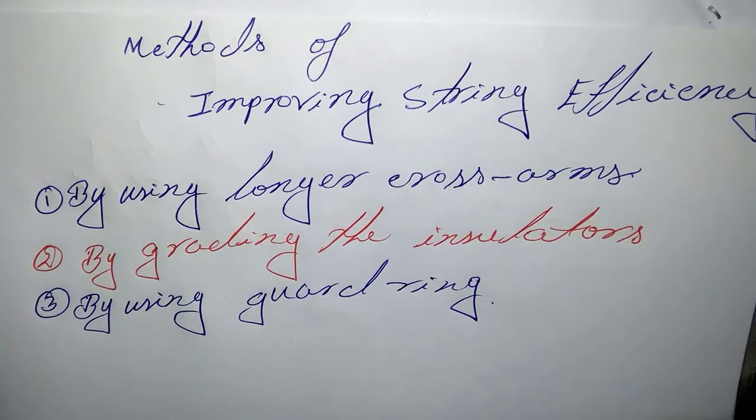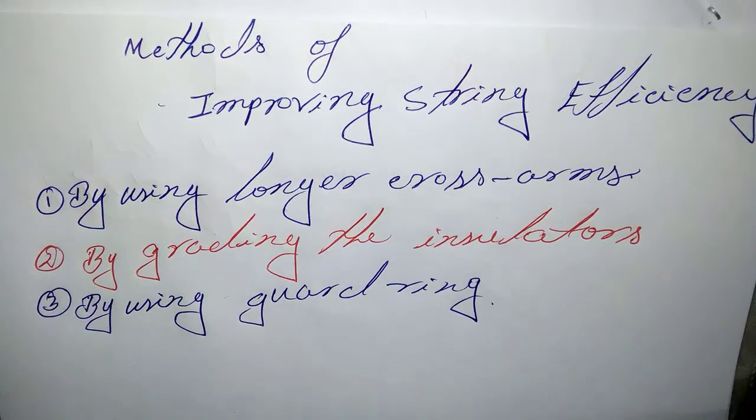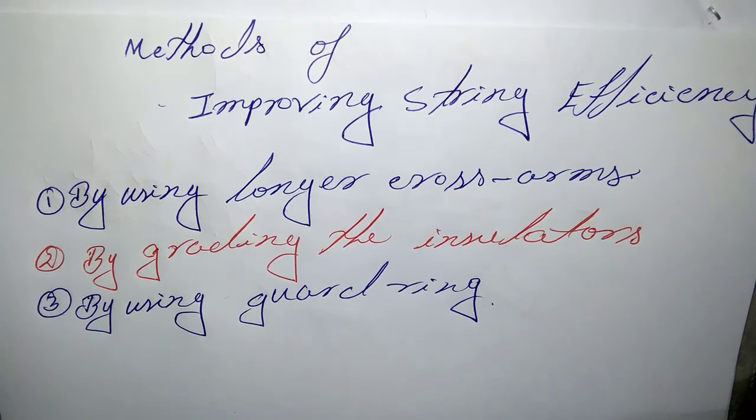Hello everyone, in this tutorial I'll discuss methods of improving string efficiency. It has been seen that the potential distribution in a string of suspension insulators is not uniform. The maximum voltage appears across the insulator nearest to the line conductor.